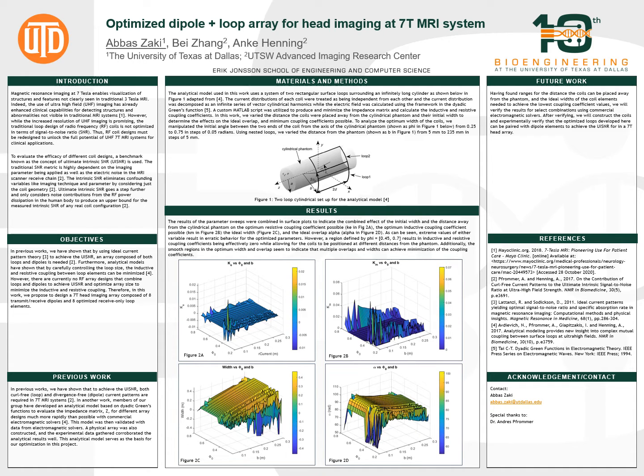And so in this paper, we utilize that analytical model with these two rectangular coils that you can see in Figure 1, along a cylindrical phantom, and vary the actual width for these two array elements, as well as the overall distance that they're placed from the cylindrical phantom.